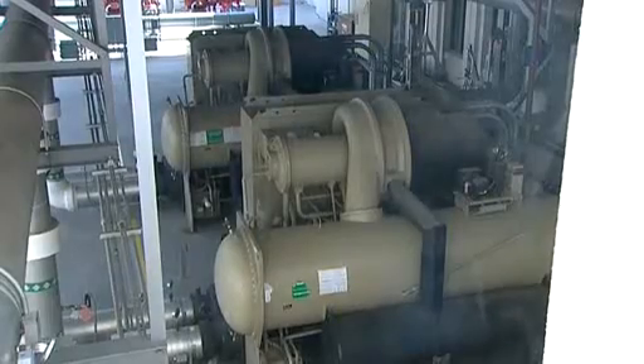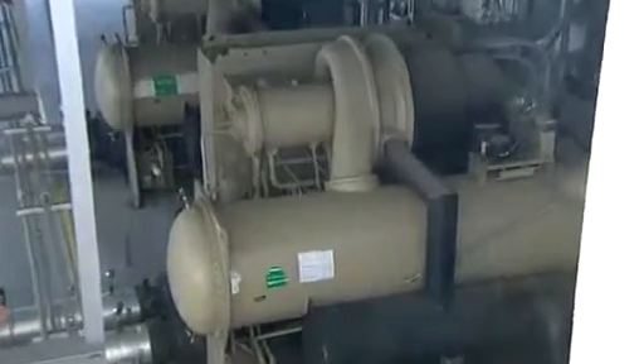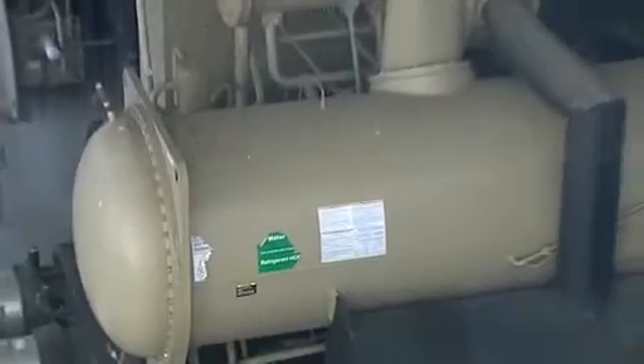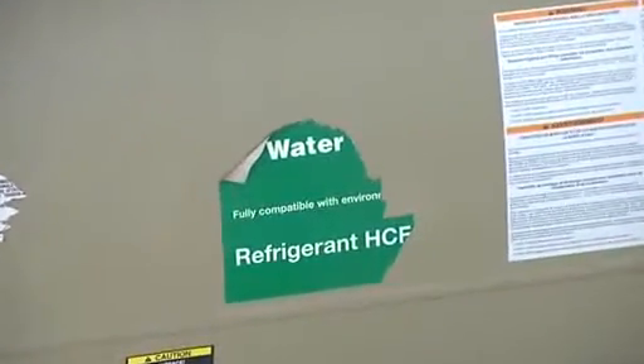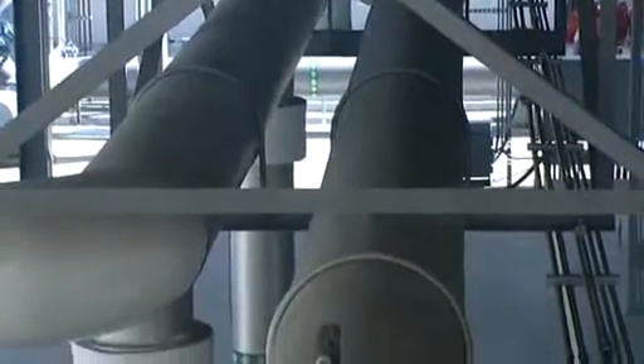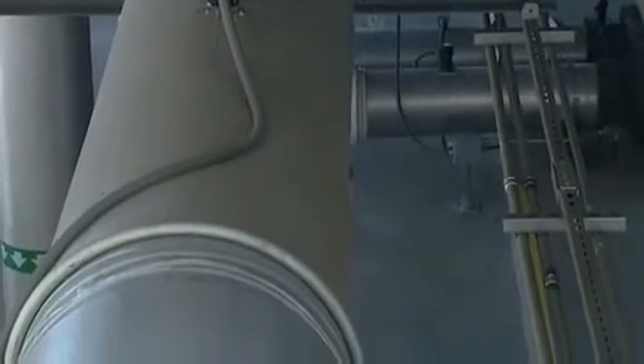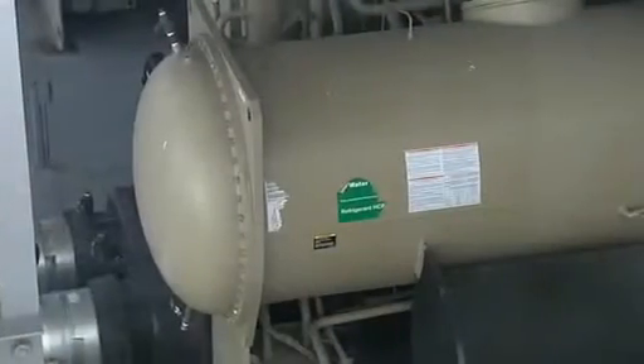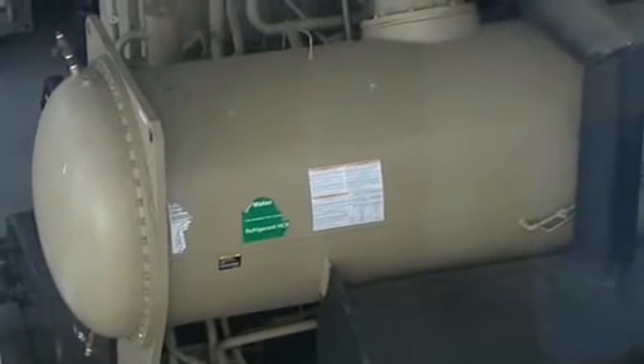So this is two 1,000-ton chillers. They're highly efficient, they're variable. So traditional data centers have a primary secondary loop, which means the primary loop is constant flow and you're wasting energy for that water, and then it's variable inside the building. What we have is a variable primary loop, which means that it's all one big loop inside and outside of the building, and all the components along that loop actually match the load that's sensed. So these chillers will go up and down based on whatever is generated inside the data center.